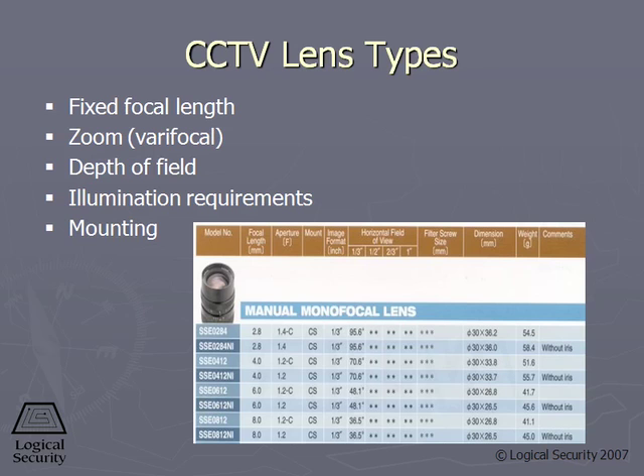We talked about lensing. We have a fixed focal length or a variable focal length. This would require much more sophistication on the part of the closed circuit TV lens. A fixed focal length is relatively inexpensive and simple, but again, it only gives you one area of focusing, one area where you can actually see what's going on. We also want to consider the depth of field. Now, this has a relationship to the aperture. The greater the aperture, the narrower the depth of field. The tighter the aperture, the smaller the aperture, the greater the depth of field. So I want to identify what area, what region or range of depth is in focus.